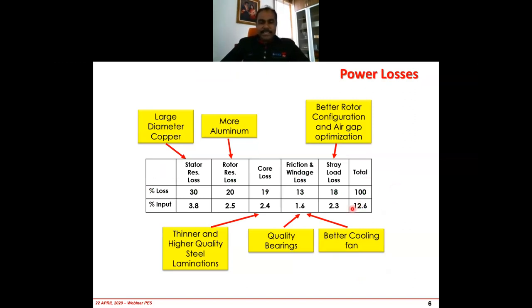If you look at a typical induction motor, let's look at the losses. Out of 100% losses, 50% comes from resistance losses. Resistance losses means I squared R loss, which is from the stator, because we have a winding there, and the rotor, which also has a winding. Current flows in both the stator and the rotor, and therefore it produces losses. So that is 50%. Then we have core loss, because we have laminated steel, the best magnetic conductor, so there are always magnetic losses. Of course, we also have the bearing, and the cooling fan, which contributes to friction and windage losses. Then we also have stray load losses, which are usually due to the air gap.